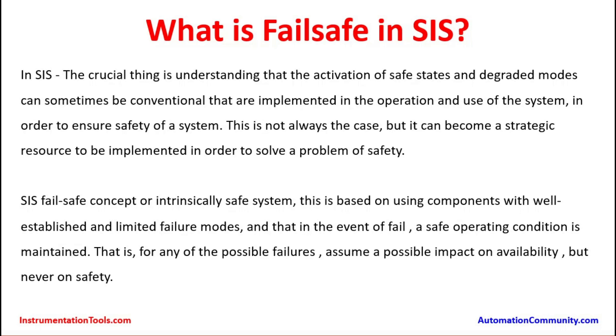For the safety instrumented system, the fail safe action is arrived at depending on process criticality and equipment availability. What will happen when a particular area goes into shutdown must be considered during the engineering phase, and the fail safe condition for the respective system instruments has to be identified.